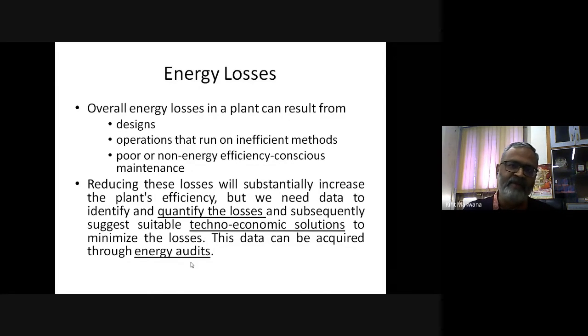So, for the sake of simplicity, they were using the most efficient compressor, that is true. But the compressed air they were using for cleaning is high pressure air, which is not at all required. So we asked them to start one other new compressor, which is quite inefficient, but because it has to deliver low pressure air, it saves energy. So there are so many inefficient methods, O&M practices and design problems. These are the issues which create the energy losses.